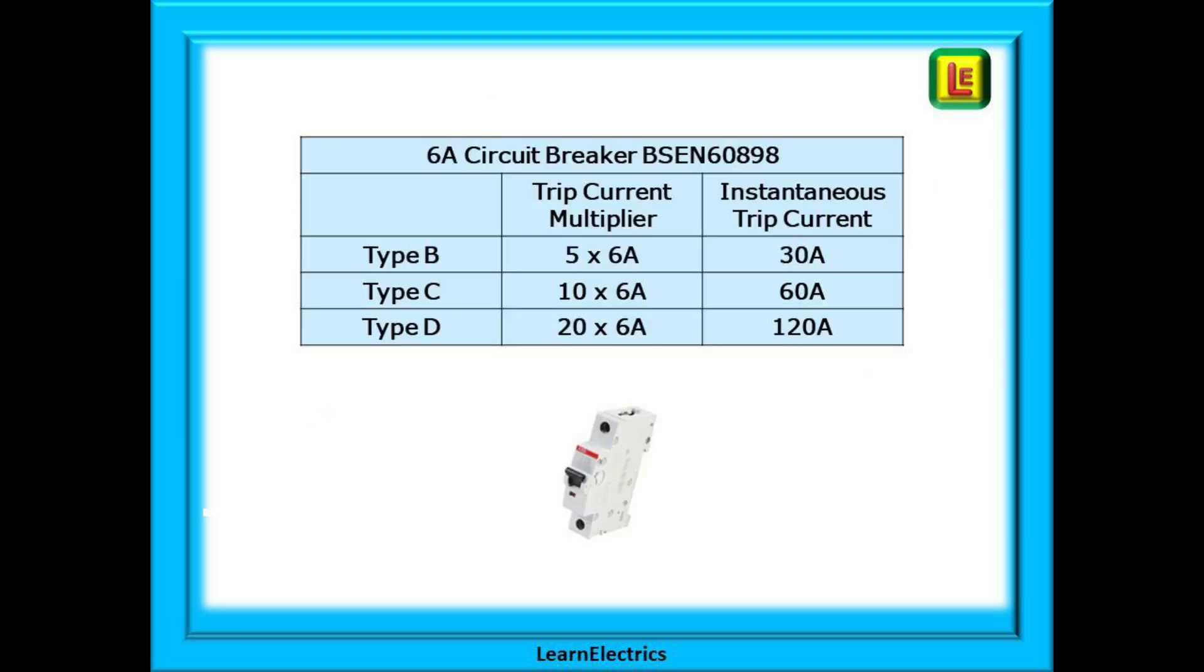Let's look at what this means to a 6 amp MCB if there was a fault at the consumer unit. Again we are looking at worst case scenarios. A type B breaker needs five times its rating to make it trip almost instantly. 5 times 6 amps is 30 amps of fault current. A type C 6 amp MCB needs 10 times the rating which is 60 amps and a D type needs 20 times 6 amps or 120 amps in order to achieve near instantaneous tripping.